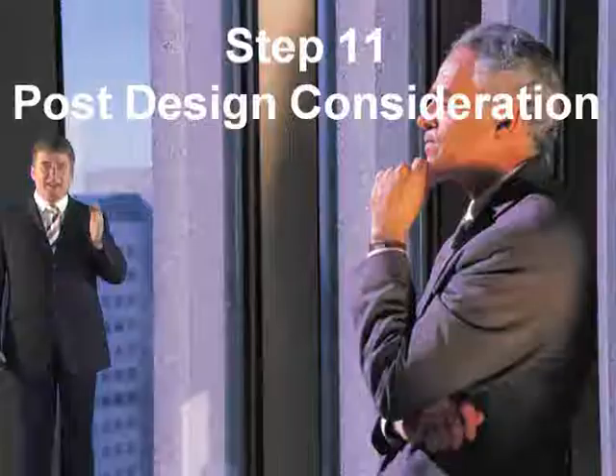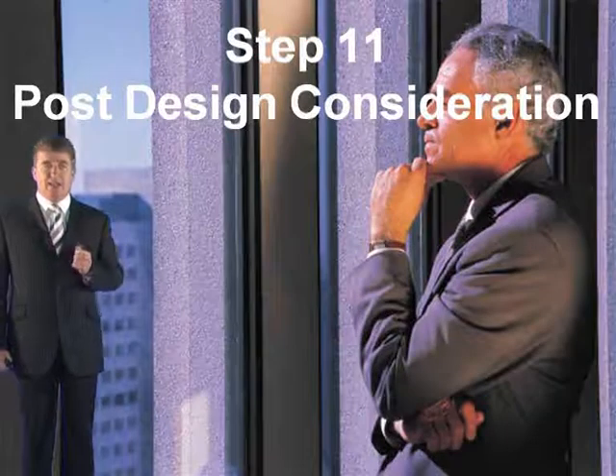The final check is step eleven — the post-design considerations. In this case, you would ensure that weather conditions would not have an adverse effect on ventilation, and that the pitch of the roof is not greater than 30 degrees. You've got to look through the wind criteria, check that curtains are not going to deflect, and look at tall buildings in the area. Those are the sort of things to look at in the post-design considerations in step eleven. That completes this exercise.